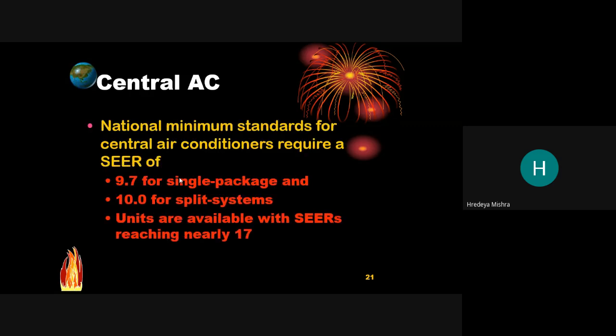Central AC. The national minimum standard for central air conditioning requires a SEER of 9.7 for single package and 10.0 for the split system. Units are available with SEERs reaching nearly 17.